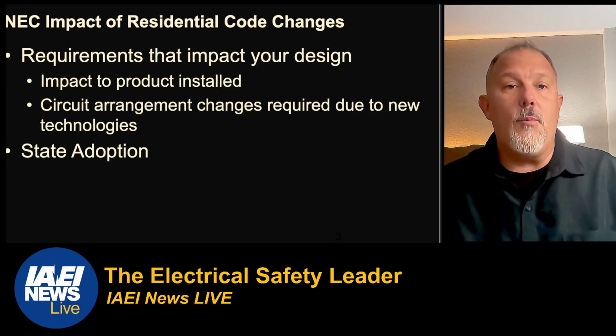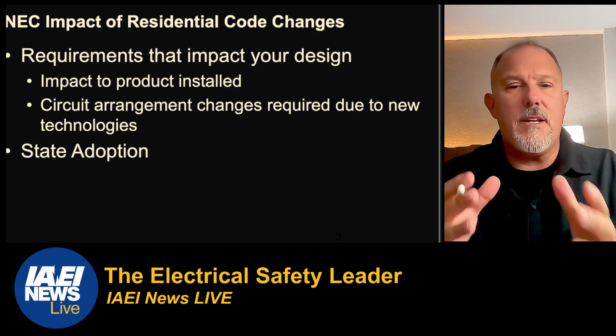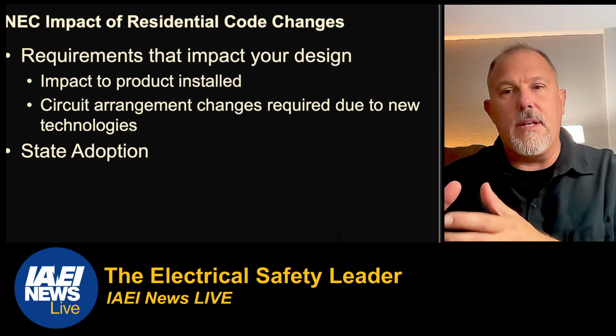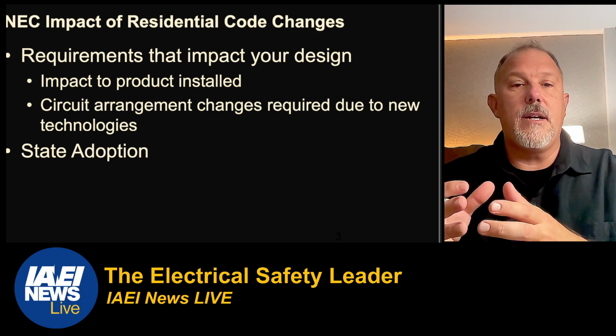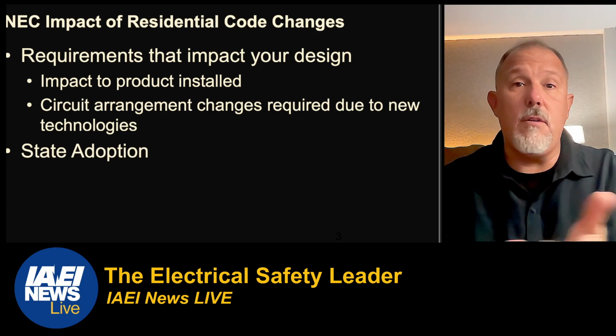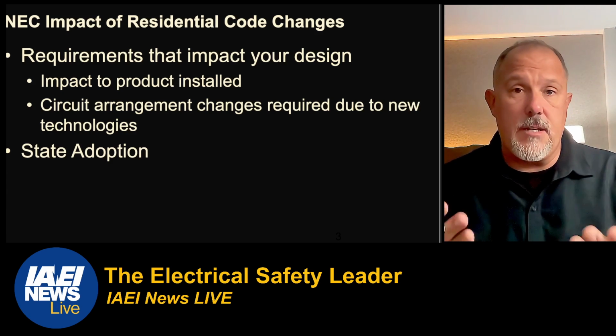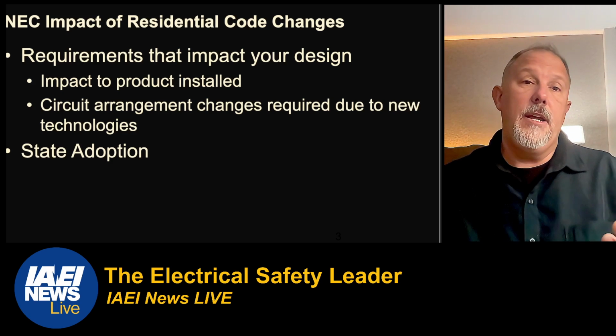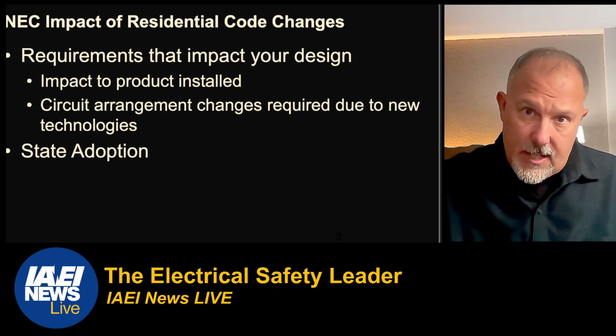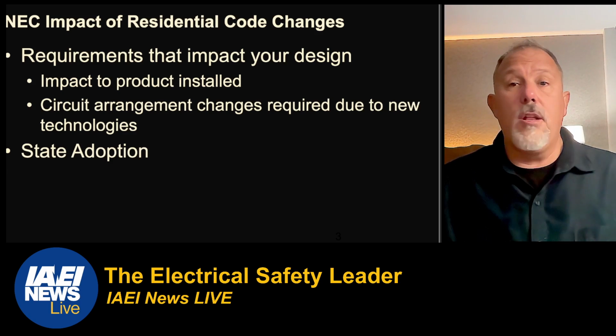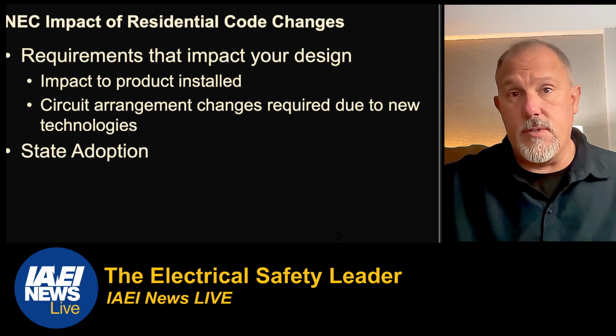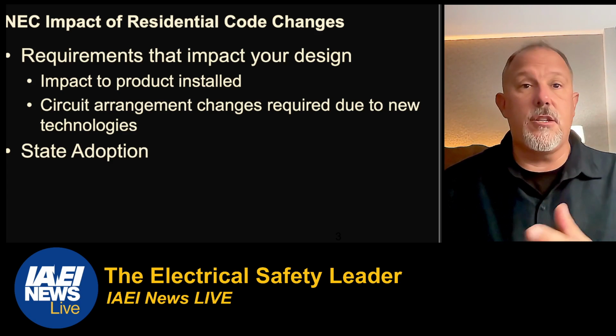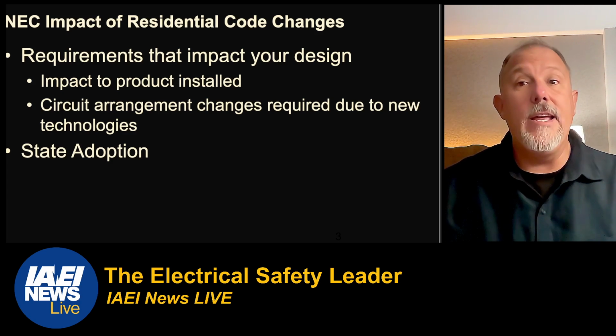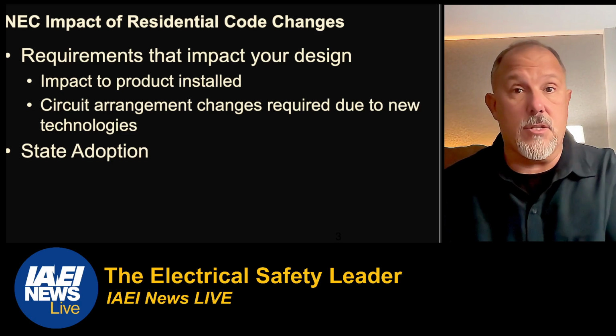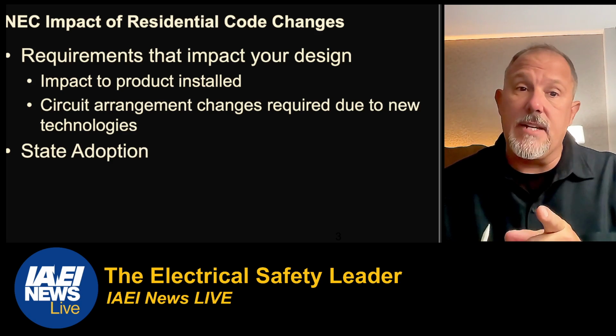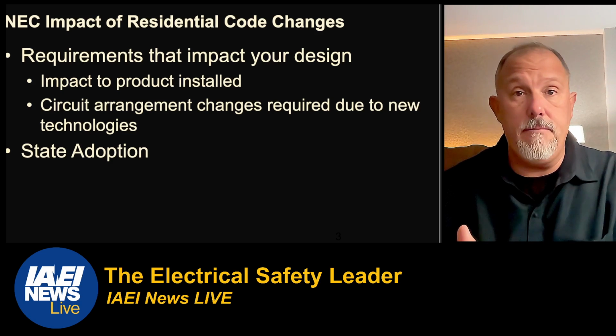All right. When you think about residential code changes, you have to think about the requirements that impact your design and maybe the product that you have to install. For example, tamper-resistant receptacles are a good example, in my opinion. If you put a standard receptacle in an application where all of a sudden there's a new requirement for tamper-resistant, it's not going to change the fact that you have a receptacle. It's just what type of receptacle is permitted to be installed there. AFCIs and GFCIs, I could say, may impact your design.